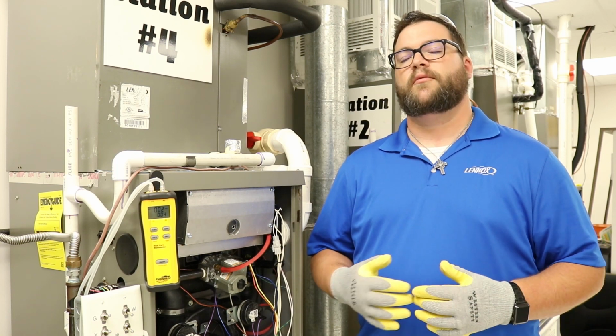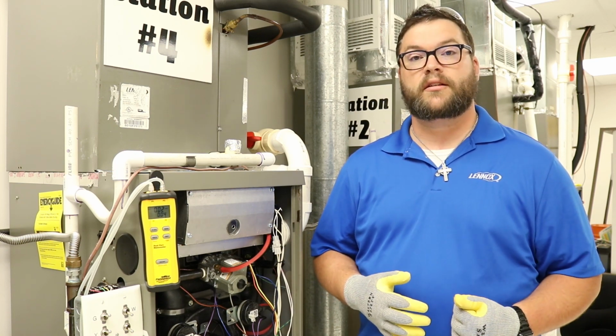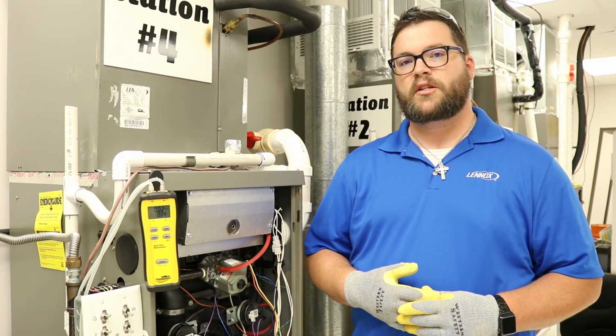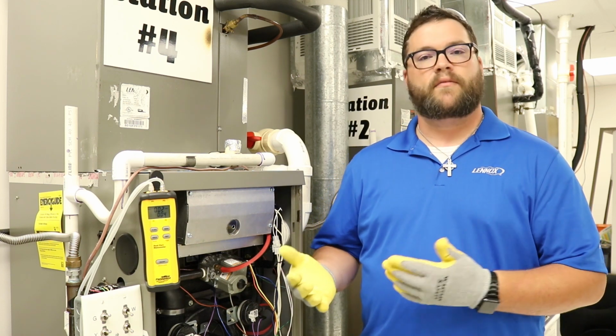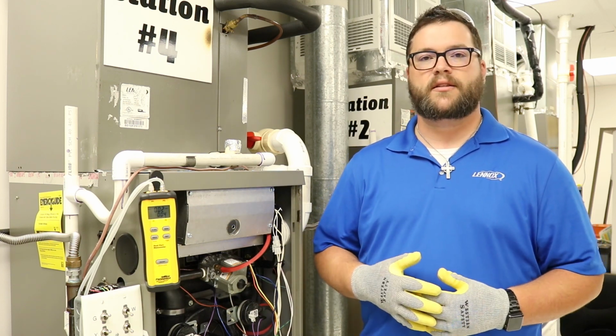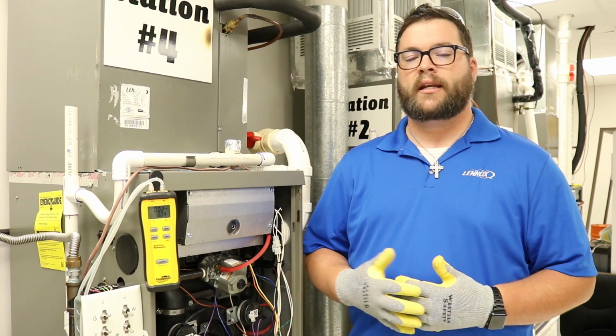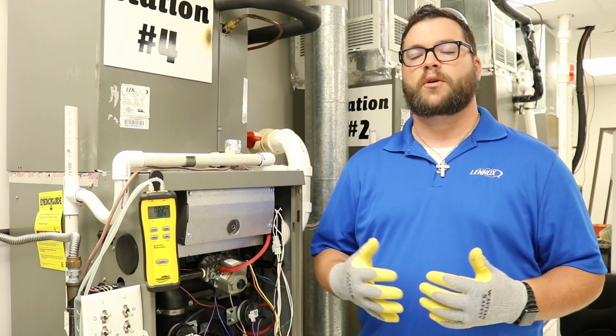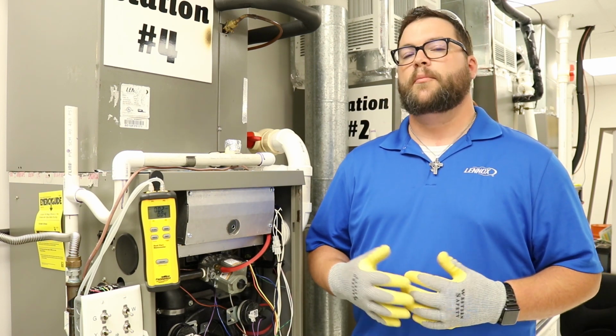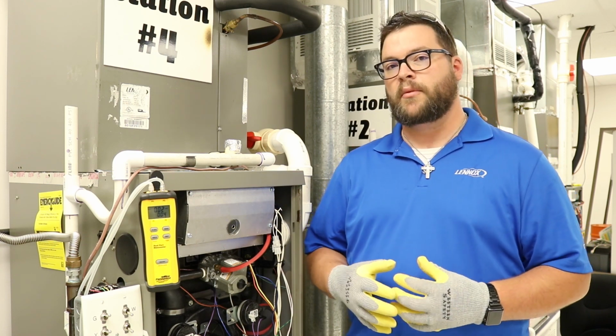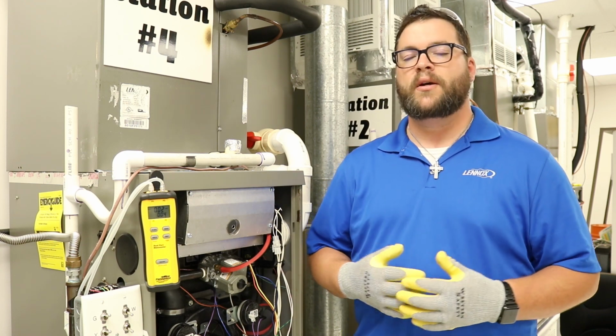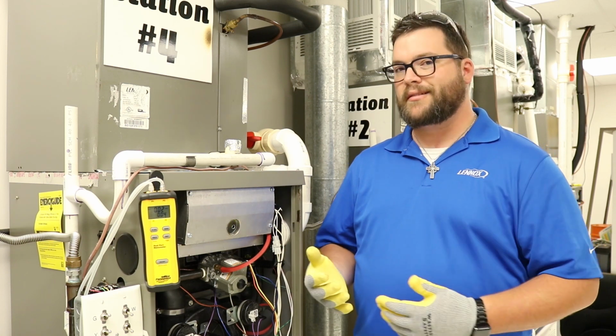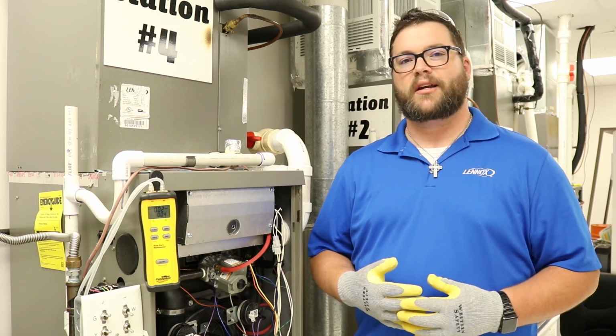Then you find yourself later on down the road putting in a compressor and you're still having the exact same issue again. Could be static pressure or airflow through that system is the main culprit. And a lot of times airflow through the system becomes more of a problem overall than not. So it's really important to understand the basics of checking static pressure, and that's what we're going to cover today.